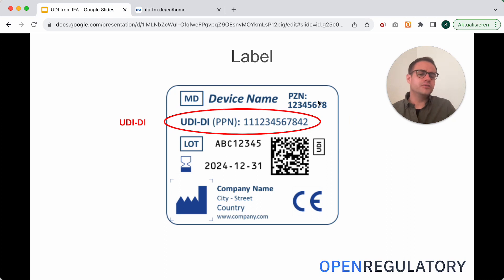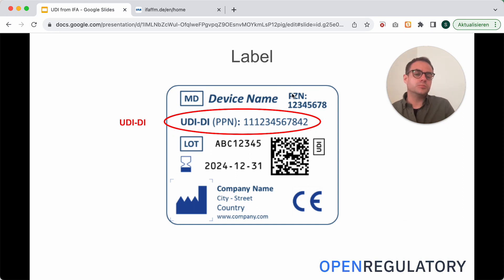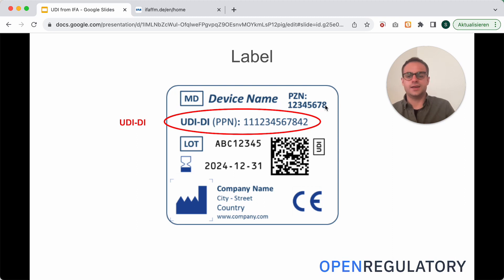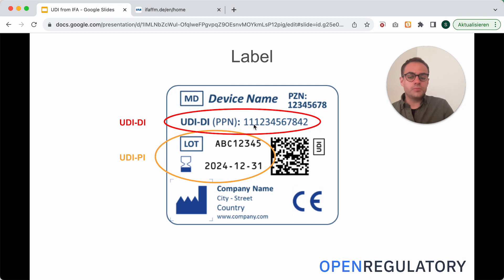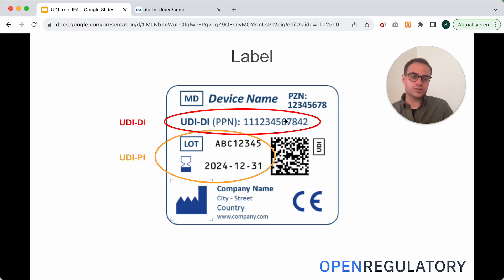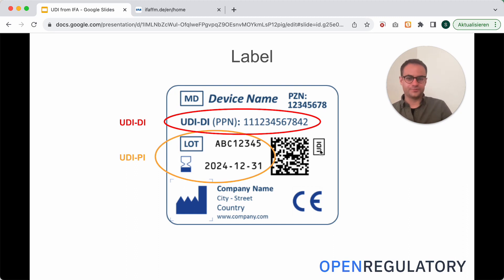If you don't want to sell your medical device through a public pharmacy, you don't actually need to put the PZN — you would only put the PPN, as the PZN would be redundant information in that case. Then you have the UDI-PI, which in this case consists of the LOT number and the expiry date. Both the UDI-DI and the UDI-PI are encoded in the data matrix code, and here's also the official symbol for UDI.